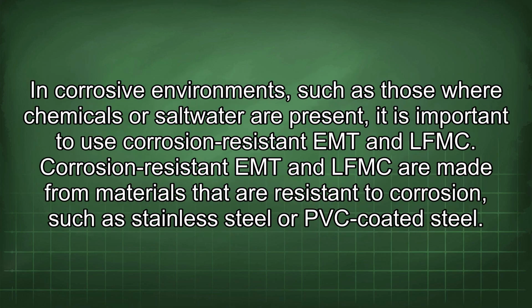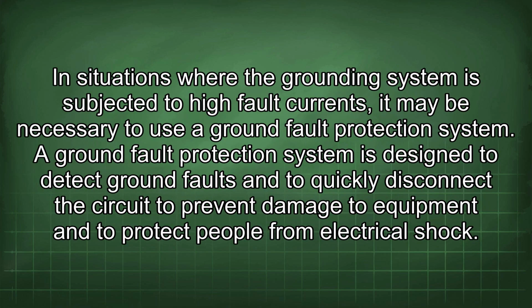In corrosive environments, such as those where chemicals or saltwater are present, it is important to use corrosion-resistant EMT and LFMC. Corrosion-resistant EMT and LFMC are made from materials that are resistant to corrosion, such as stainless steel or PVC-coated steel. In situations where the grounding system is subjected to high fault currents, it may be necessary to use a ground fault protection system. A ground fault protection system is designed to detect ground faults and to quickly disconnect the circuit to prevent damage to equipment and to protect people from electrical shock.